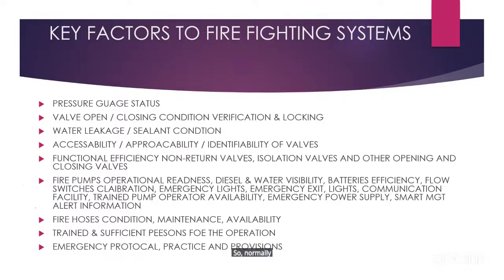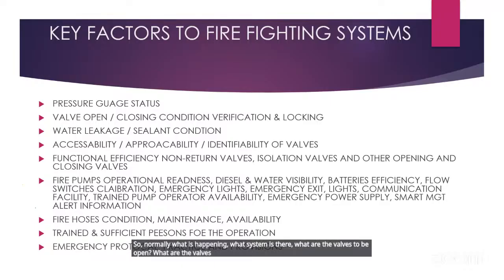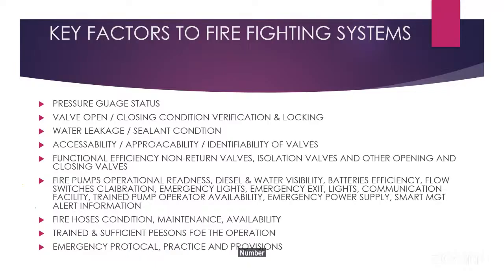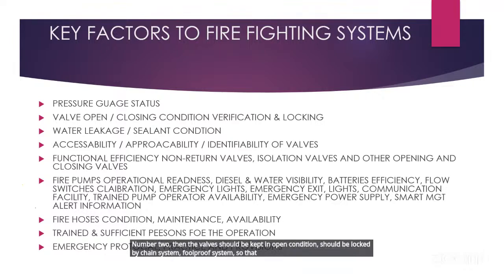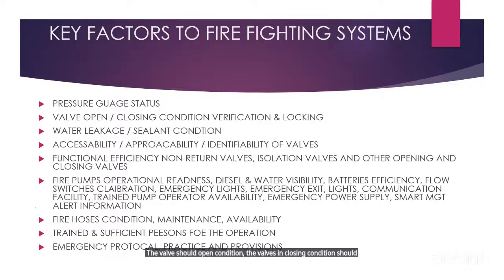So normally, what system is there, which valves are to be open, which valves should be kept in open condition, and which valves should be kept in closed condition? That must be identified and listed out first, number one. Number two, the valves that should be kept open should be locked by a chain system, a foolproof system, so that nobody can inadvertently or intentionally close or open the valve, and the system will not get affected. Bad intention could not work out. So that is the condition. The valves should be kept in open and closed condition and locked in such a way that nothing will happen by anybody or by fault also.